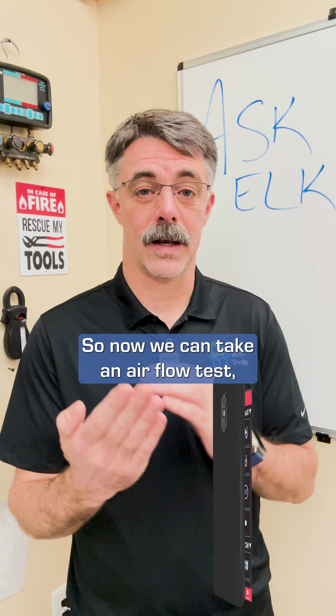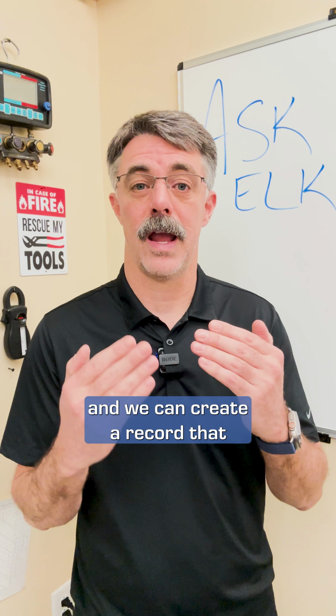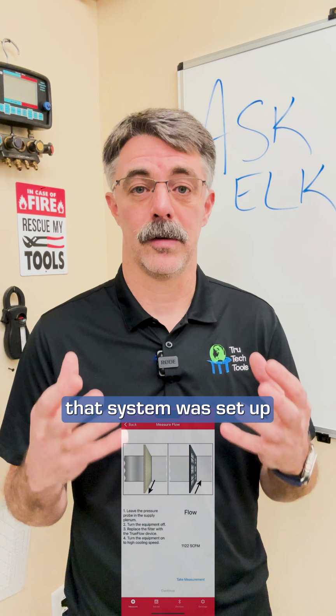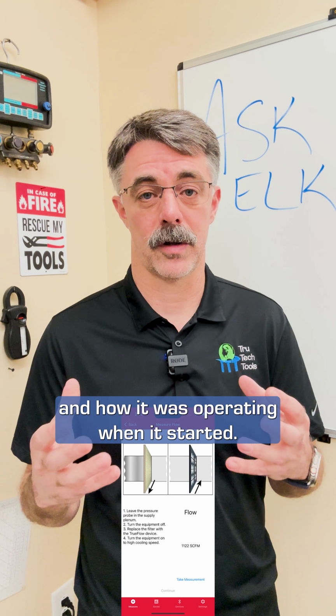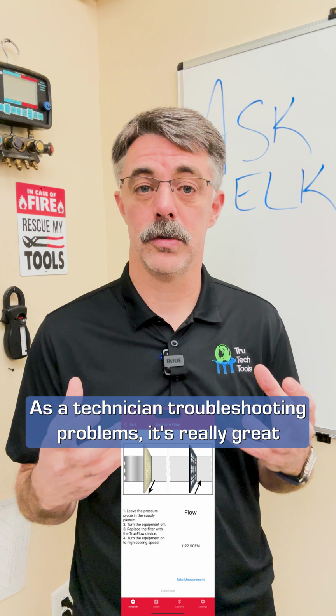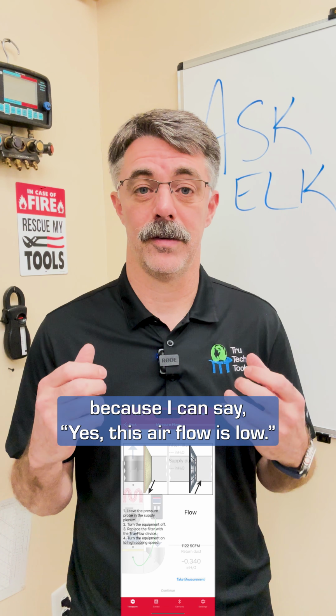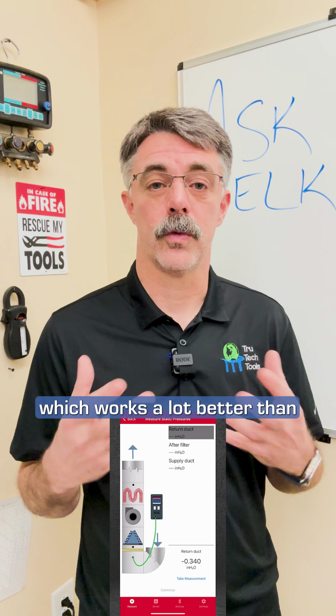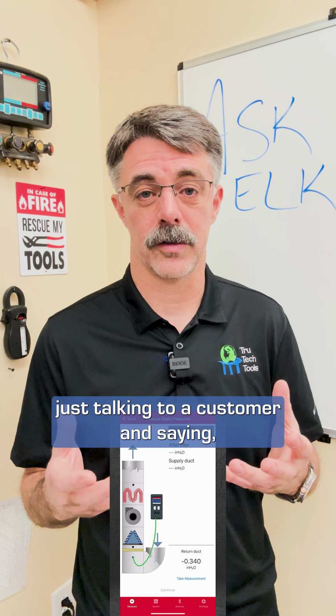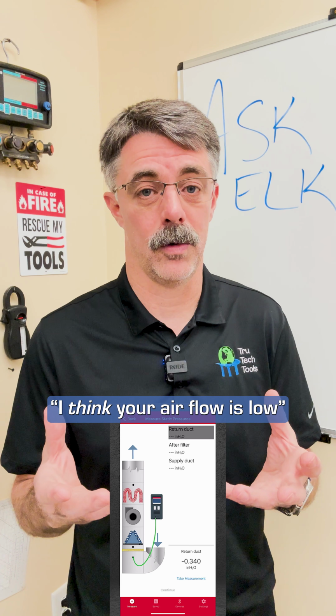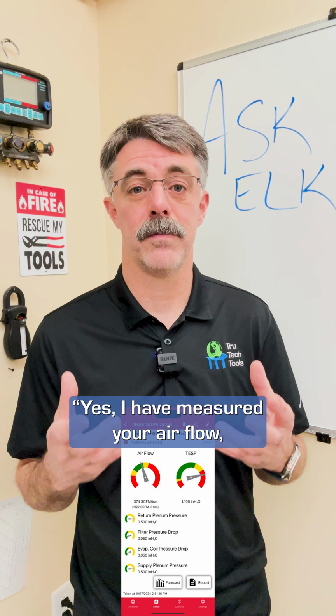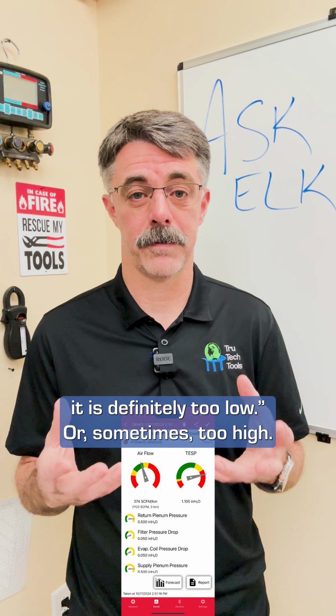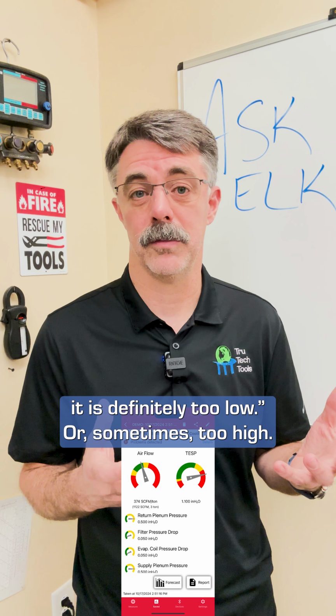So now we can take an airflow test and a static pressure test, and create a record of how that system was set up and operating when it started. As a technician troubleshooting problems, it's great because I can say, yes, this airflow is low, which works a lot better than just telling a customer I think your airflow is low. Now I can say, I have measured your airflow, and it is definitely too low, or sometimes too high.